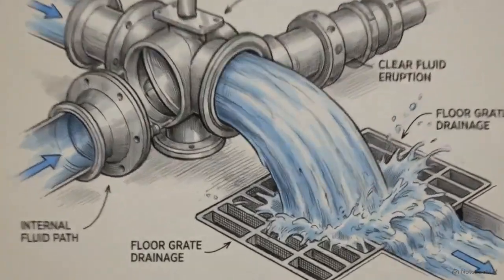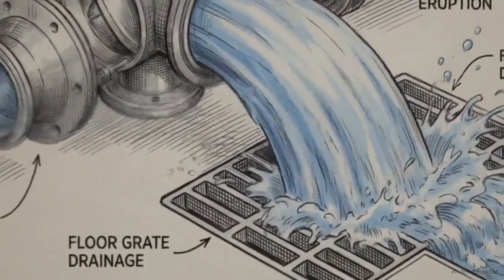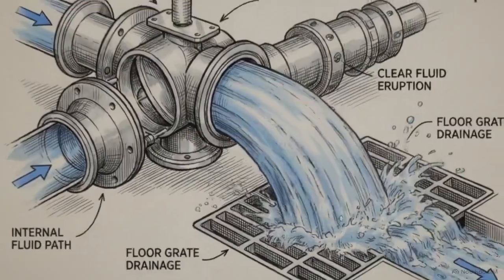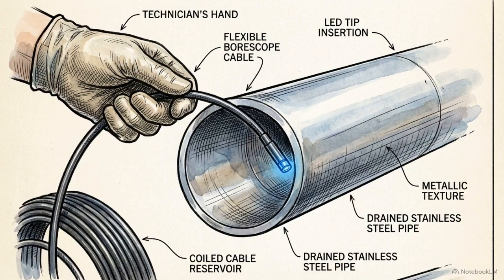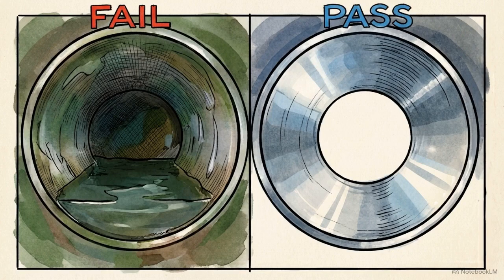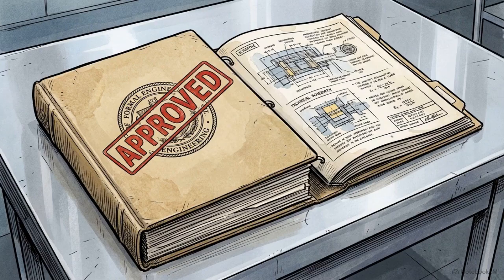We fill the system completely and then perform a full gravity drain. After the drain, we use a borescope or moisture sensor to inspect the line. If the screen shows a bone-dry interior, as seen on the right, the system has successfully drained. This physical proof must be captured in the Commissioning and Qualification, or C&Q, turnover package.